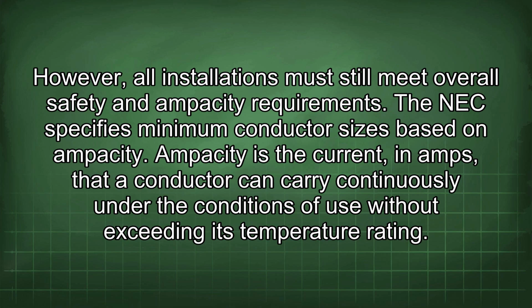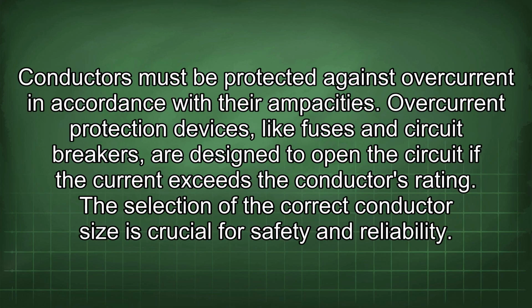The NEC specifies minimum conductor sizes based on ampacity. Ampacity is the current, in amps, that a conductor can carry continuously under the conditions of use without exceeding its temperature rating. Conductors must be protected against overcurrent in accordance with their ampacities. Overcurrent protection devices, like fuses and circuit breakers, are designed to open the circuit if the current exceeds the conductor's rating. The selection of the correct conductor size is crucial for safety and reliability.